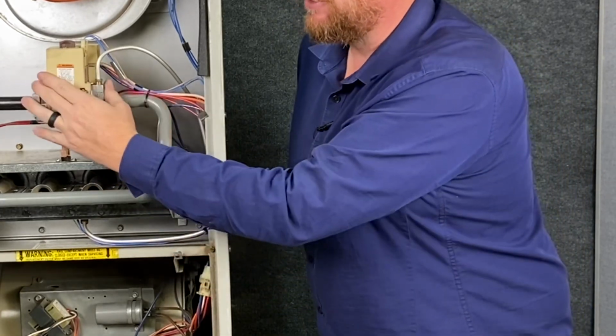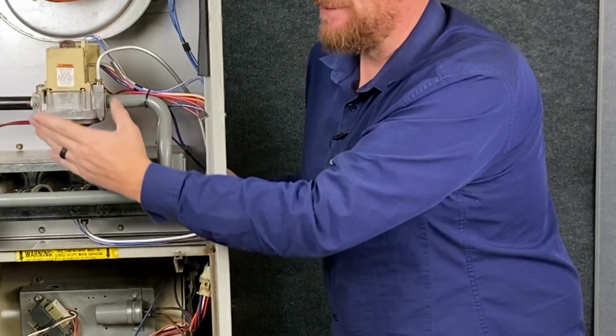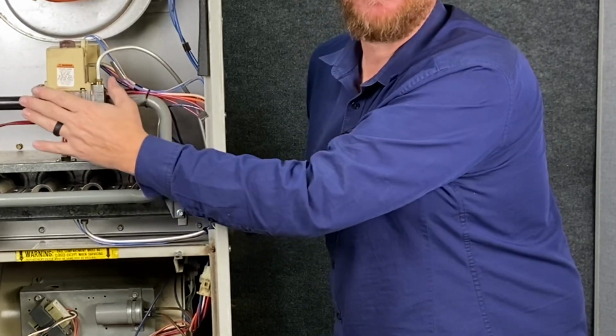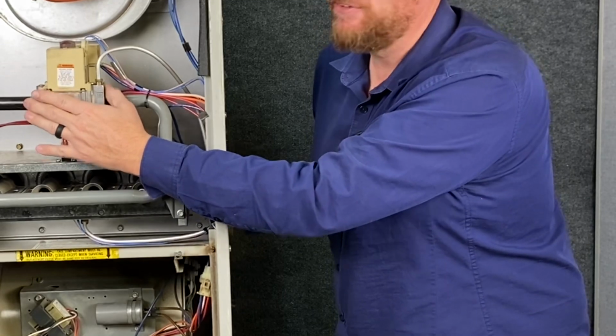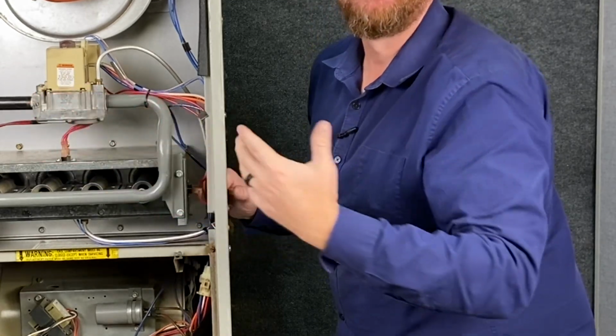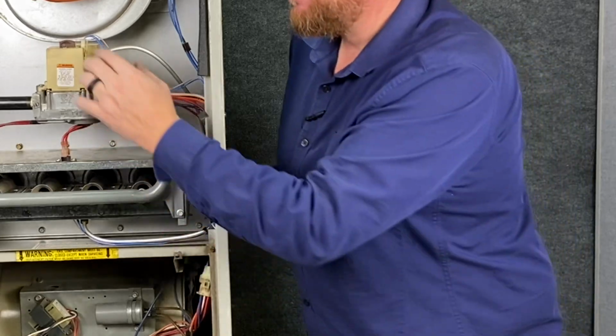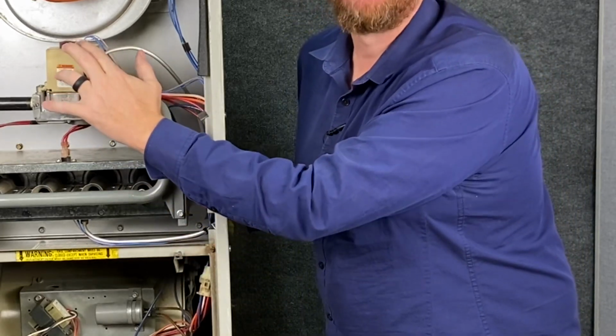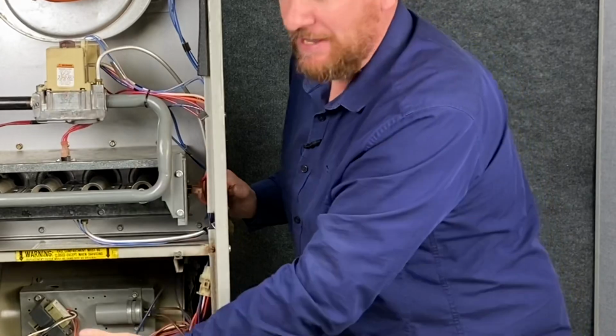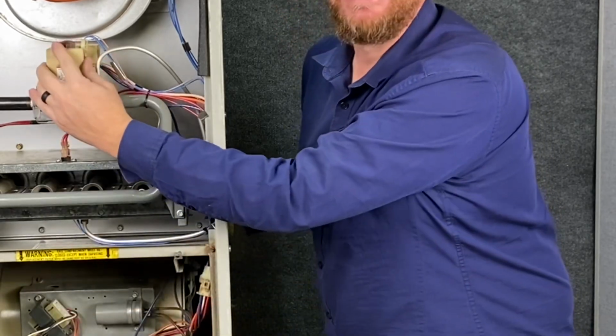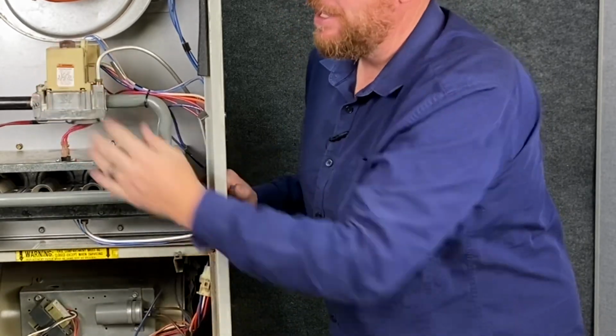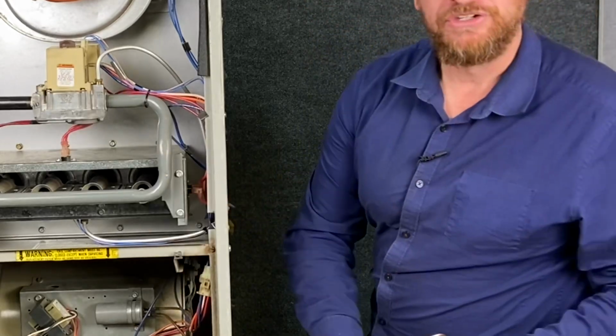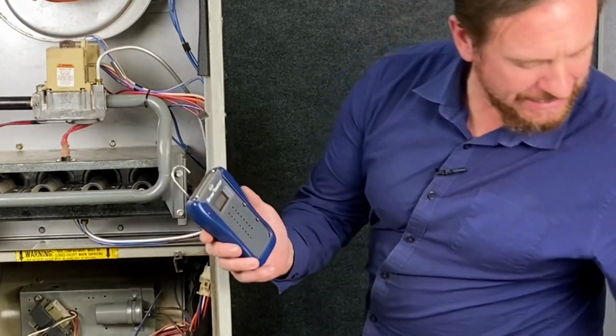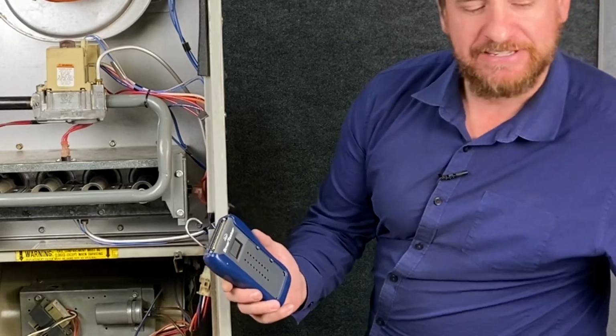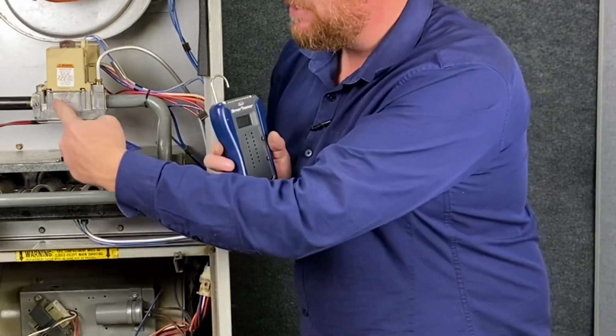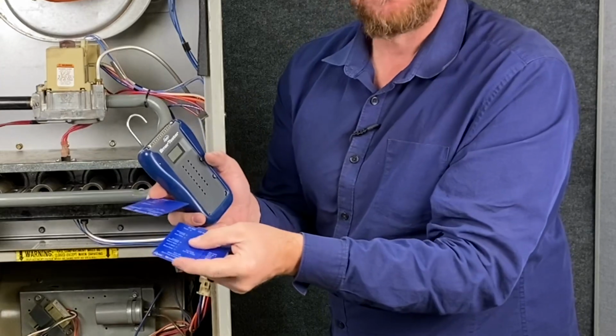Now, this particular combination gas valve has a special name. They're called smart valves. There's two different manufacturers that made them, Honeywell and White Rodgers, but both of these worked very similarly. There were different modifications and times with them, but they required slightly different steps for servicing and diagnosing. We had our main IFC, plus also behind here there's another little control board in this as well. So they make this cool little tool that you can hook up, you can plug in, and you had many different options for what size you need. And so you would match up the model number of the gas valve to one of these little cards.